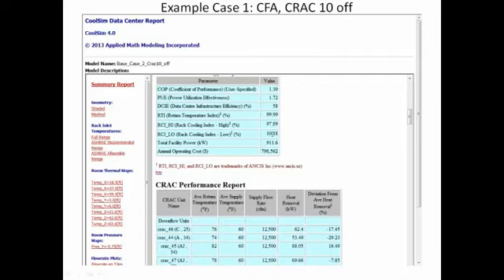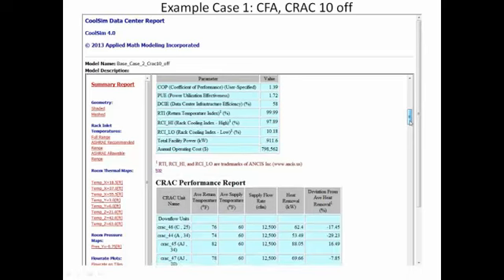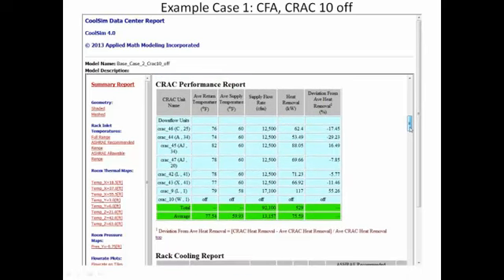What's kind of interesting is the low came up. Now the reason the low came up, I'm still shooting air out at the same temperatures, but it has to do with mixing in the room. Because there's less total air, there's only 92,000 CFM of total air. I took 17,000 out. Then my return temperatures in my worst case conditions went up a little bit. They were 12 degrees. Now I'm getting those up to 14, 15 degrees, that sort of thing, in my worst case conditions. So it's interesting.